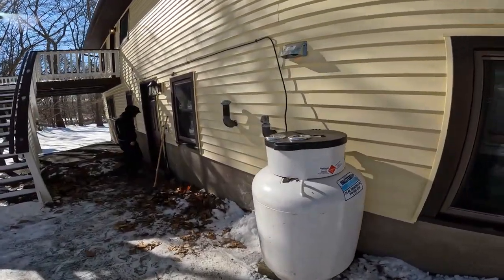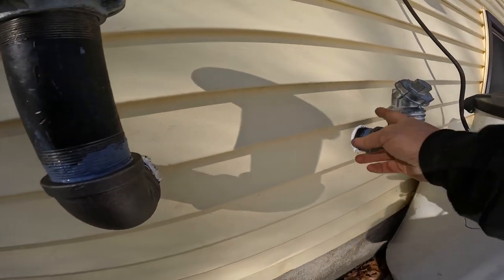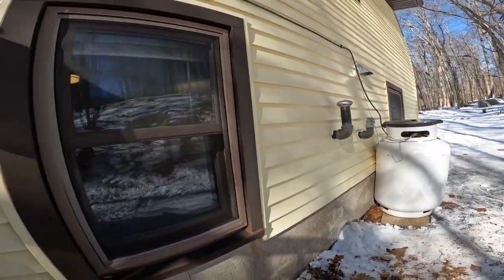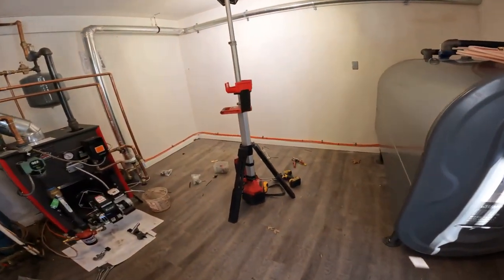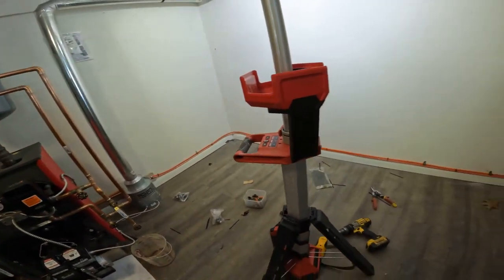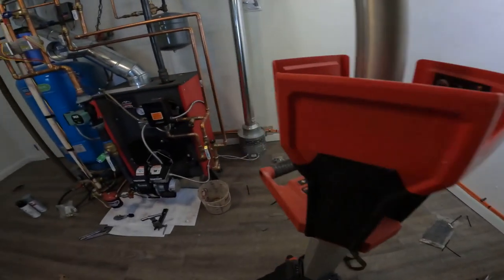So Sammy's got this all completed now. All marine caulk there. So we'll paint that now, and then we'll put the escutcheons on, and we'll caulk those escutcheons. And if you can see, the vent pipe is 6 inches higher than the fill, which is code. Yeah, very nice. That's all secured, zip tied. It's got those vibration clips on it. You know, we keep it a little bit off just in case somebody kicks it. They don't kick the copper and crimp it closed.